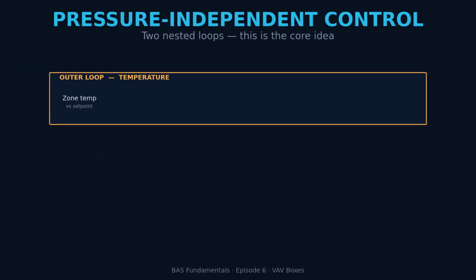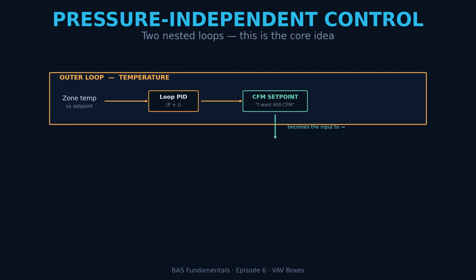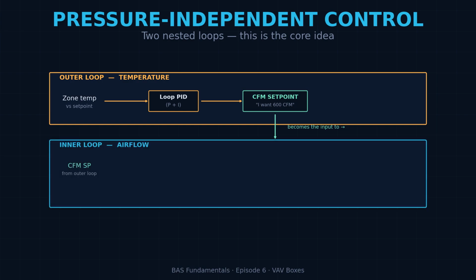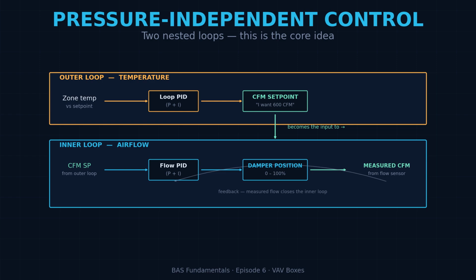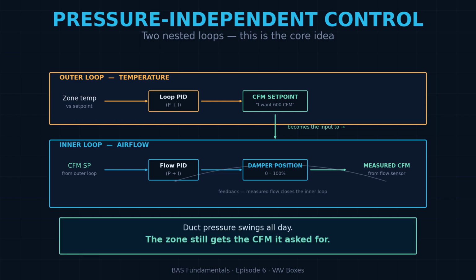Now the core control idea, this is where most techs lose the plot. A VAV box runs two nested control loops. The outer loop is temperature. The zone thermostat compares zone temp to set point and generates a CFM demand. Too warm means more cold air, so demand goes up. The inner loop is airflow. It takes that CFM demand as its set point and modulates the damper to hit it. This is called pressure-independent control, because duct static pressure can swing all day long and the box still delivers the CFM the zone asked for. Pressure-dependent boxes, which just position the damper directly, drift all over the place when the AHU ramps up or down. Nobody installs those anymore, but you'll find them in old buildings and you'll hate them.